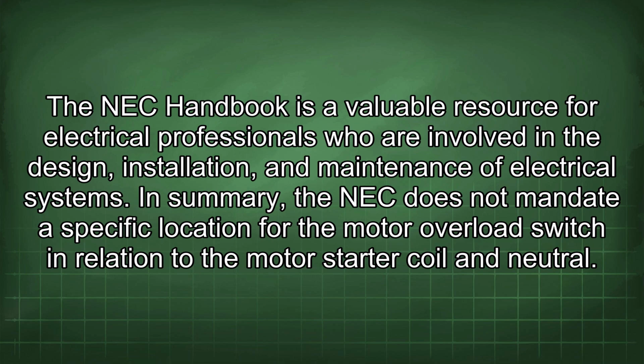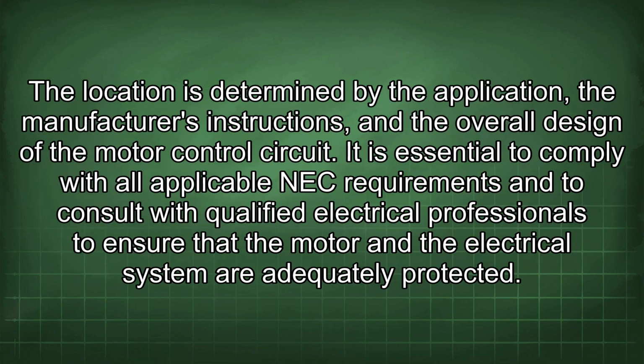In summary, the NEC does not mandate a specific location for the motor overload switch in relation to the motor starter coil and neutral. The location is determined by the application, the manufacturer's instructions, and the overall design of the motor control circuit. It is essential to comply with all applicable NEC requirements and to consult with qualified electrical professionals to ensure that the motor and the electrical system are adequately protected.